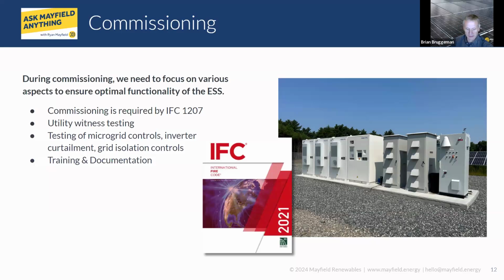Also during this commissioning phase, there'll be a lot of testing and tuning of the controls to verify that the energy storage, the generator, and the solar all work together correctly. The solar inverters need to be able to be curtailed properly and everything disconnects properly. And then there also needs to be training and documentation left with whoever is operating and maintaining the system. So that all needs to be done too during the commissioning phase.